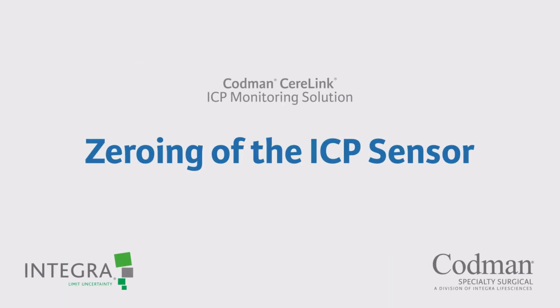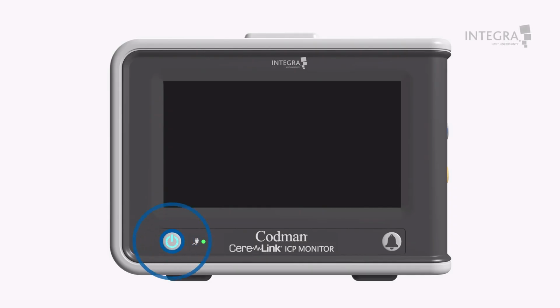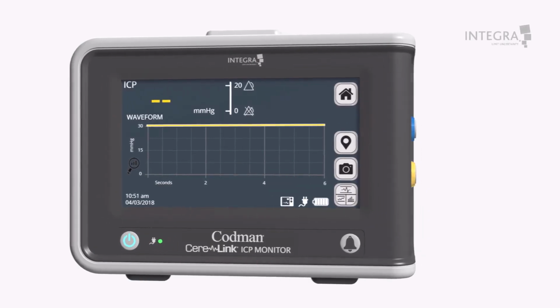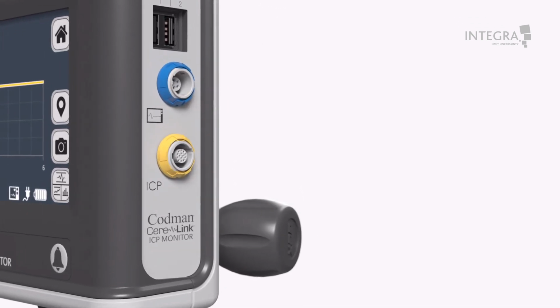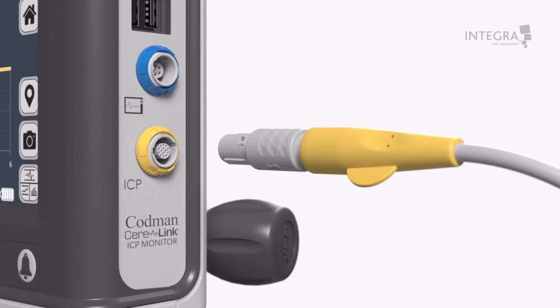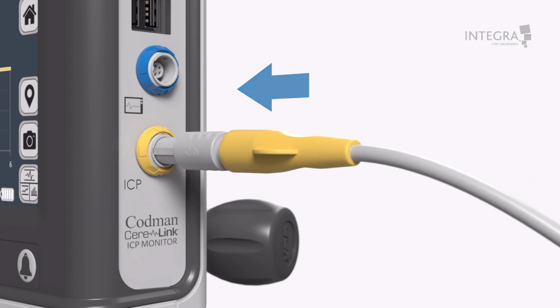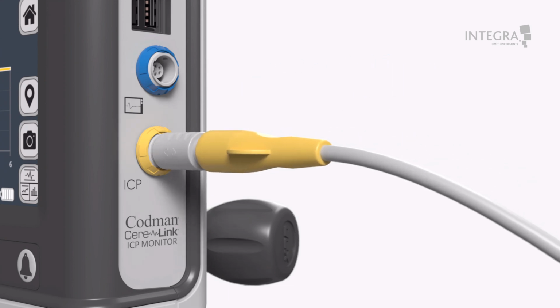1. Zeroing of the ICP sensor. The ICP sensor must be zeroed to atmospheric pressure prior to implantation. First, switch on the monitor. Connect the ICP extension cable to the yellow connector on the CereLink. The extension cable connector tab and arrows should face forward, in the same direction as the CereLink screen. Push the yellow connector into the yellow port until you hear a click. If you need to disconnect it at any time, this connection uses a pullback release mechanism and not a twist lock.